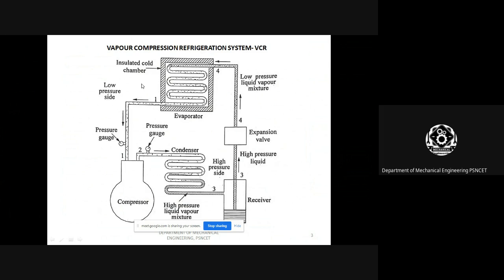One is the exit of the evaporator. Low pressure, low temperature vapor refrigerant enters the compressor. In this compressor, the low pressure, low temperature vapor refrigerant is compressed into high pressure, high temperature vapor refrigerant. It is measured by means of the pressure gauge provided at the exit of the compressor. This 1 to 2 is the process of compression from low to high.